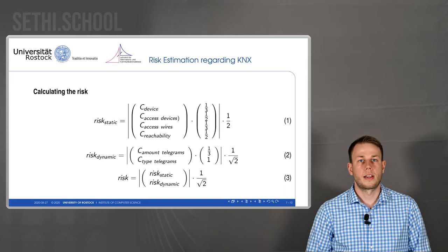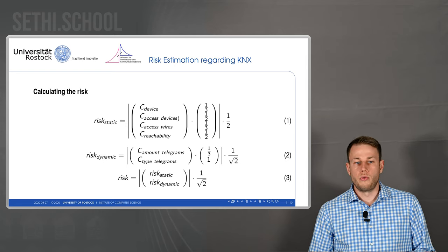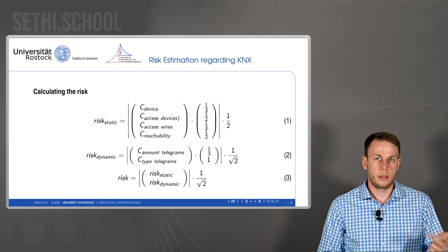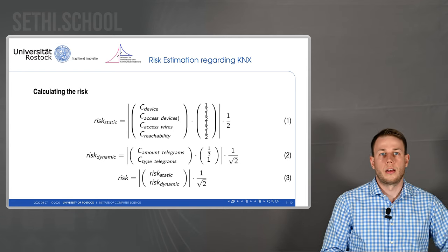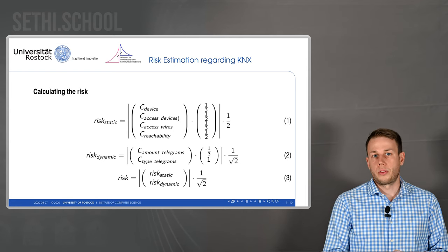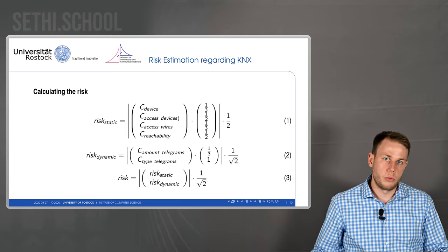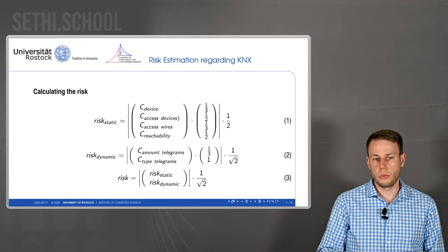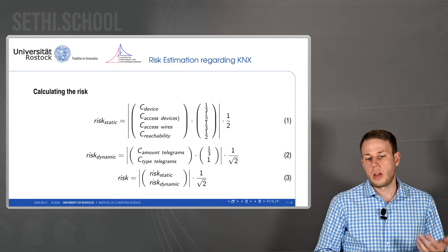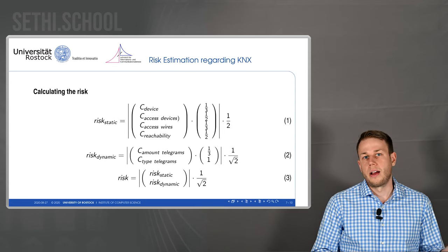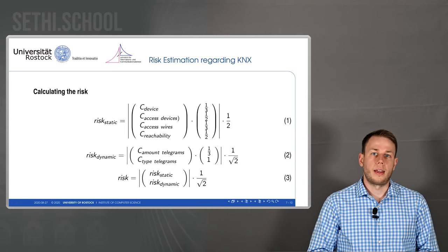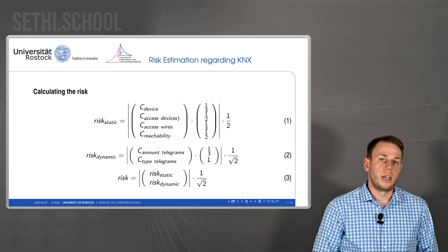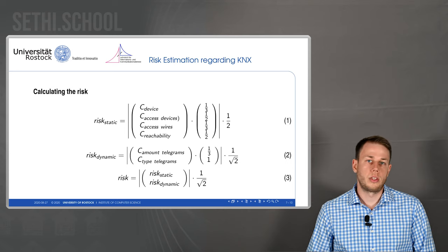After considering all these classes, we can calculate a risk for every network segment. If you have devices of class 1, 2, and 3 in a network segment, you have to consider the highest risk level — class 3 — for the whole segment, as one segment is always a transparent part of the network. We can normalize this to a numeric value and then compare values across different parts of the network to find which is the most endangered part and where additional countermeasures should be implemented.